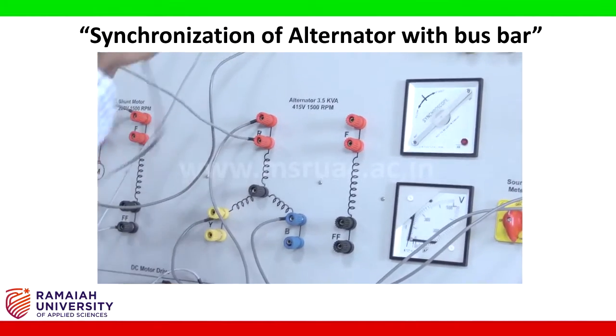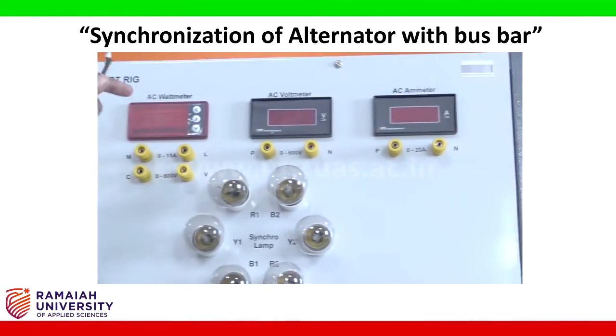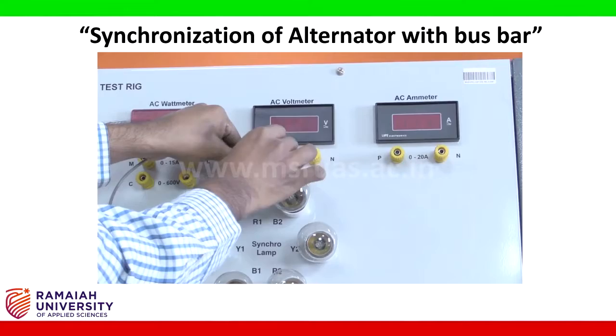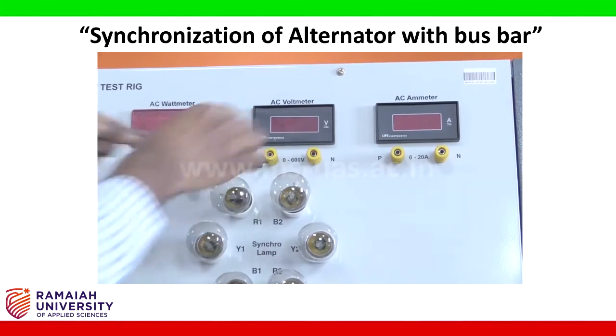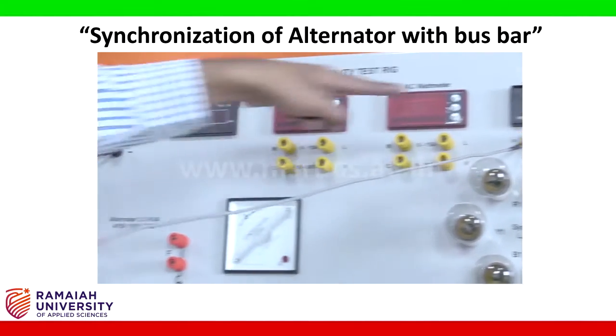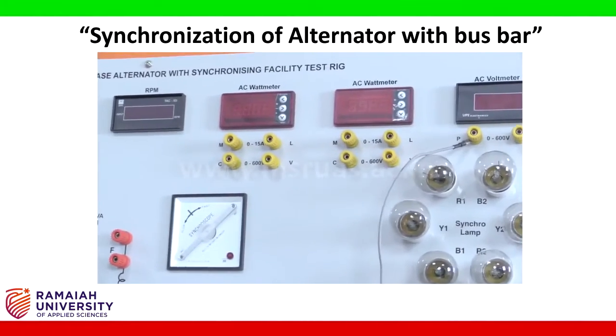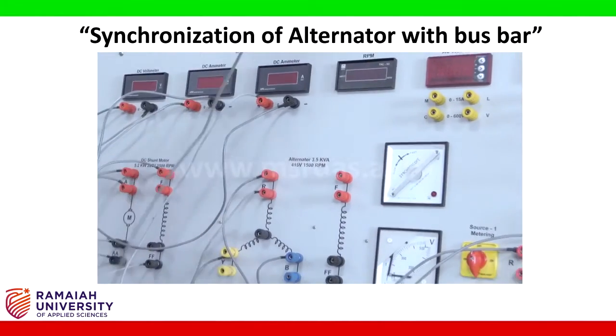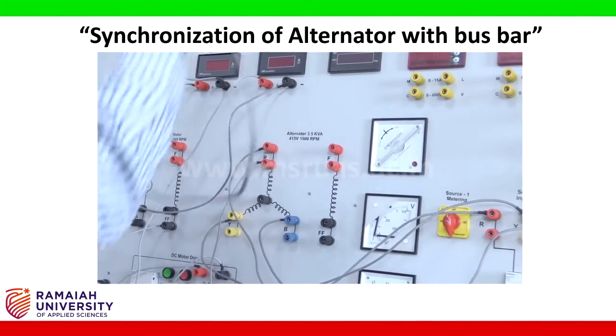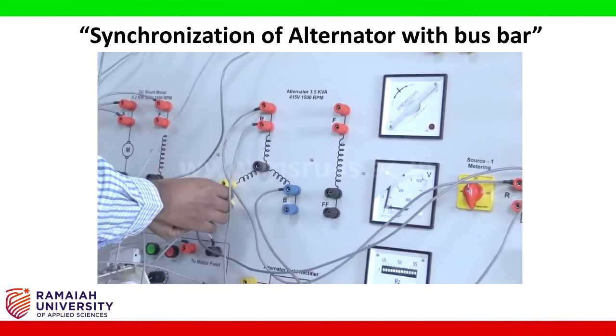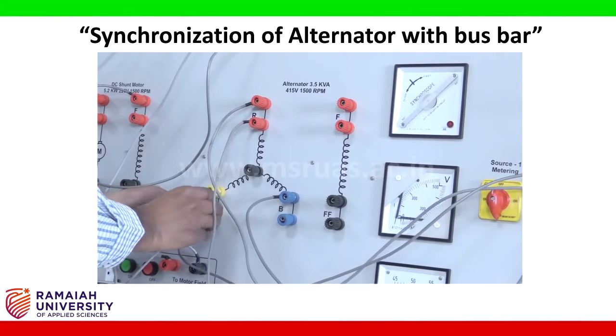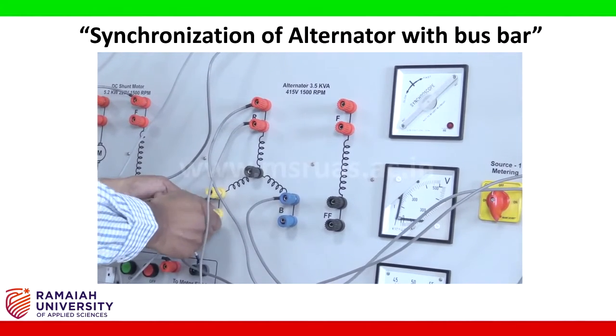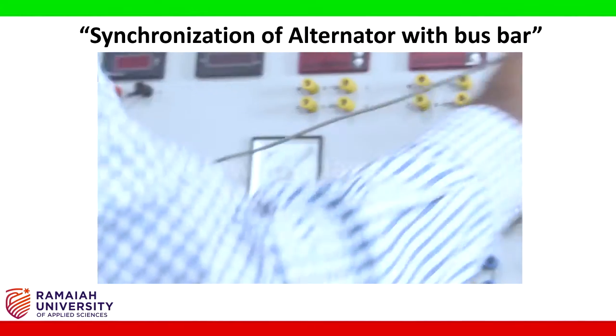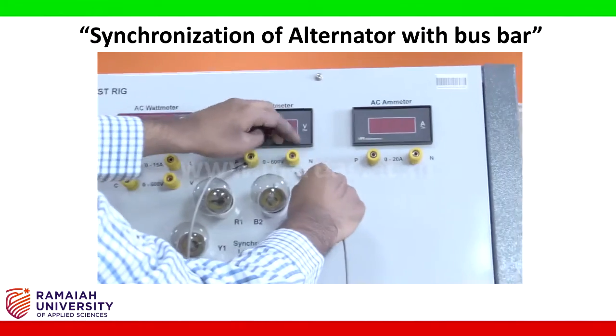Connect the voltmeter across any two terminals of the alternator. Now we are connecting a 0 to 600 volt range AC voltmeter across R and Y terminals. This is connected between R and the AC voltmeter. Take another wire and connect from Y terminal to the other terminal of the voltmeter.